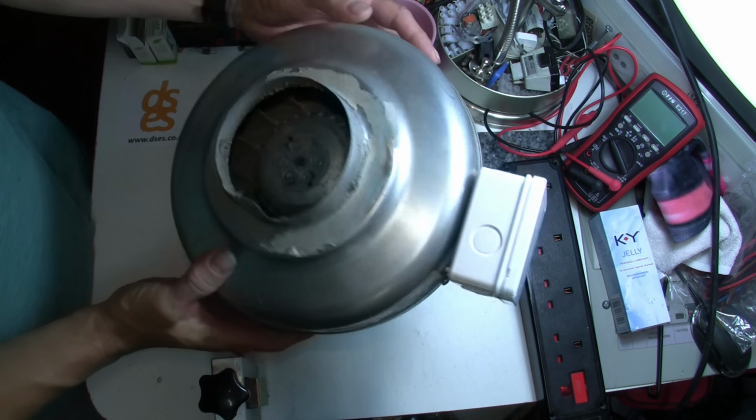Oh, how nice. I'm seeing that rogue voltage on switch line again, and it's causing bathroom 2 to flash. You know, maybe that's not a fault after all, but a characteristic of these Manrose products with such a low wattage LED lamp. I'm getting about 36 volts with this lamp connected. Let's remove it and see what happens.